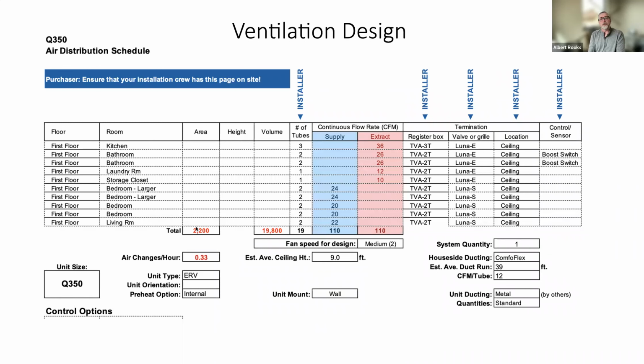If we look 2 columns to the left under area, we're going to see that this space is 2,200 square feet. So if we have 110 CFM continuously flowing into this 2,200 square feet, the next column to the right shows that the total volume is 19,800 cubic feet. Essentially, the box down below the 2,200 square feet is going to show in red 0.33 air changes per hour. So essentially, if we take that 2,200 square feet, that's roughly 20,000 cubic feet in volume, and we give it a continuous 110 CFM airflow, we're going to turn over the volume at a rate of 0.33 air changes per hour, or we're going to refresh the entire building once every 3 hours.